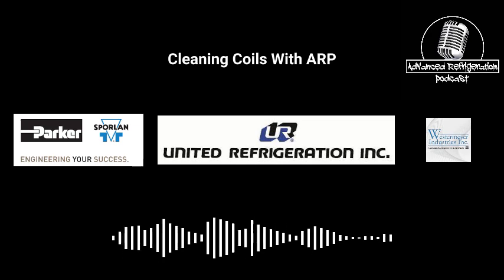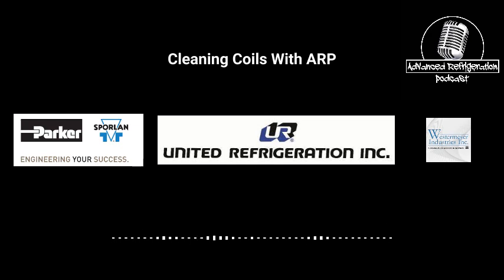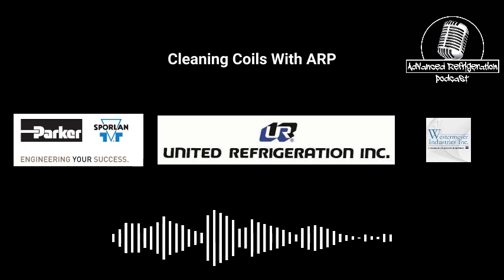You want to do it from the top down. You don't want to do it from the bottom up because you're going to push all that stuff in there, even if you're cleaning it at an angle. I know it is what it is on service calls. You've got to wash it off, and if you're going to do it, wash it off at an angle. Don't wash it straight up. Wash it back and forth at an angle so you push everything forward instead of up into the coil.